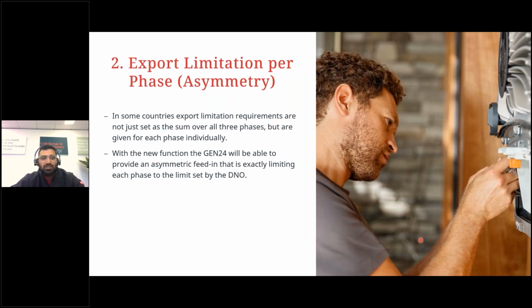Export limitation per phase. As we know, Gen24 SIMO inverters work phase-balanced in backup power mode. We now have the possibility to do asymmetric feed-in limitation with them as well. In some countries, export limitation requirements are not just set as the sum over all three phases, but are given for each phase individually. So with this new function on Gen24, we'll be able to provide an asymmetric feed-in that is exactly limiting each phase to the limit set by the NSP.